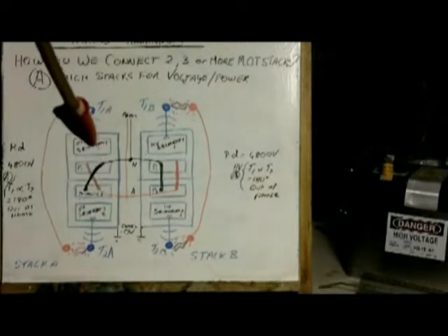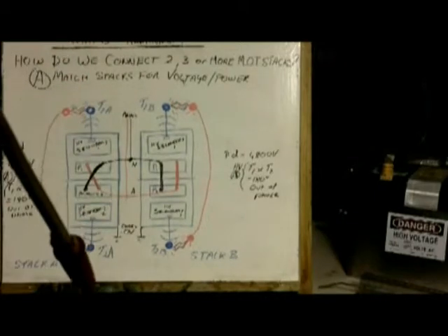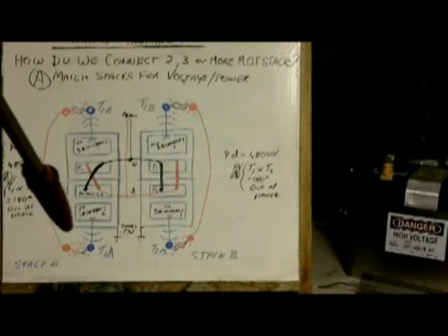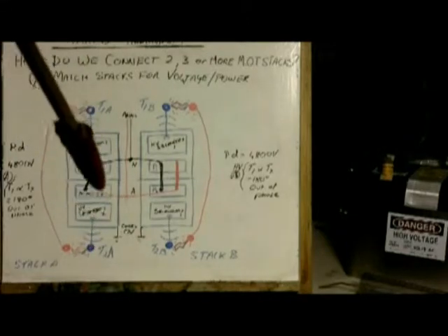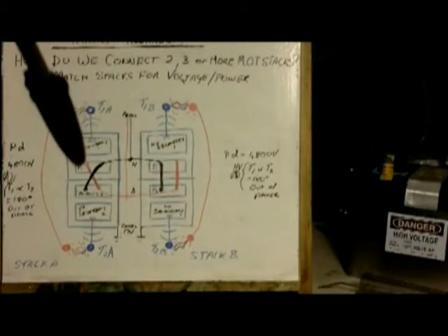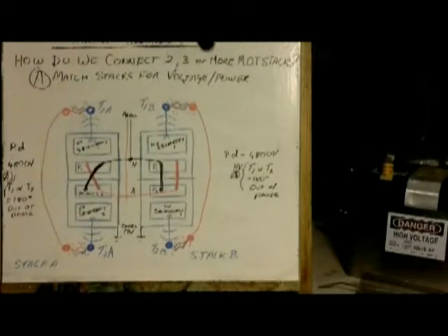Okay, another thing that you want to consider is that these two units, now that they're hardwired together, they act like one single unit. Think of it as just one transformer. Okay, that's one, that's the other, with the two high voltage ends there and there, each one delivering 2,400 volts or thereabouts, depending on what units you've chosen to create the stack. Okay, so we have a total of 4 terminals to deal with. So what do we do? How do we connect them together?